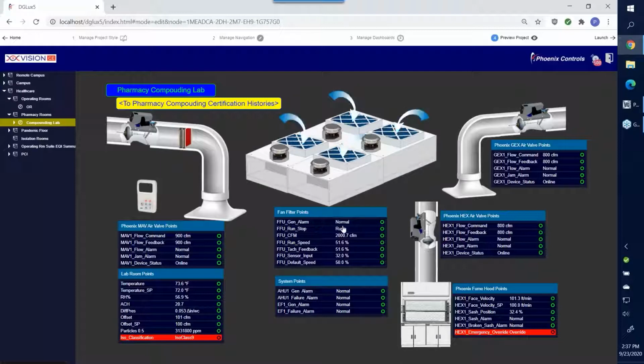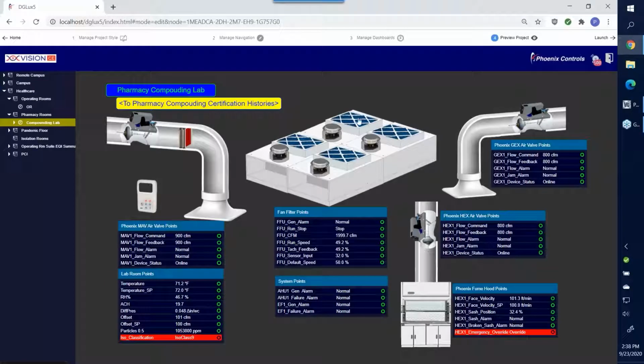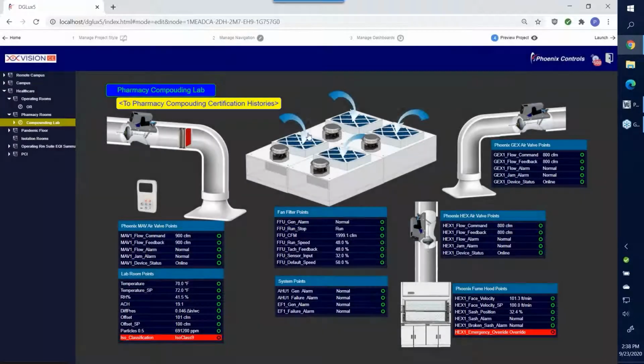Not only from a standpoint of validation, but even control, where if there was a means of wanting to turn something off, either individually—in this case we're showing where we could turn off a bank of fan filters and/or turn them back on—have some sort of analytic that we could determine that certain fans should be on. You could even have additional fans as backup, so that you could service some of the fan filters with HEPA filters and have the other ones running so you wouldn't lose any downtime.